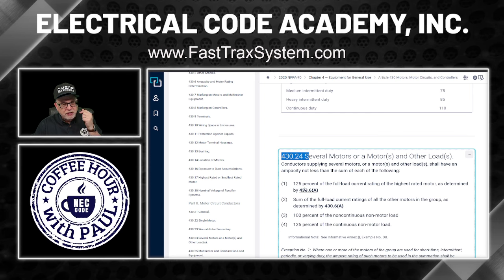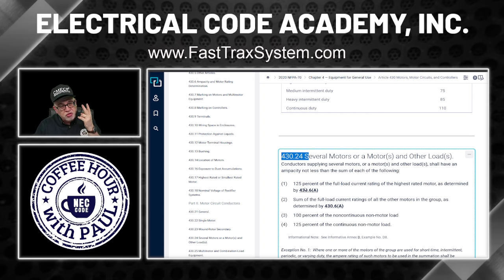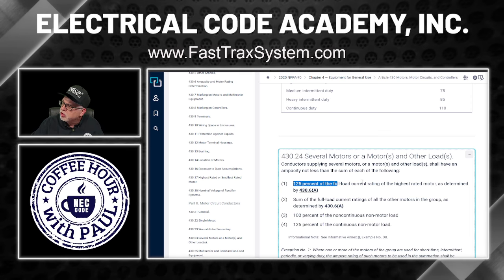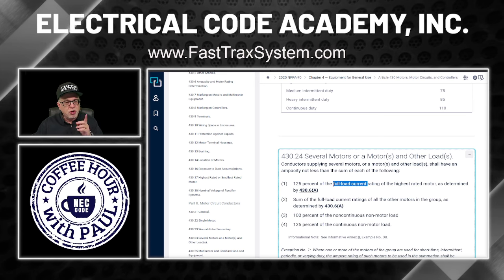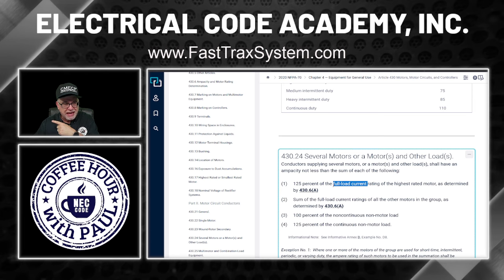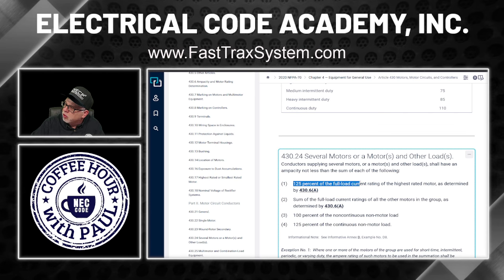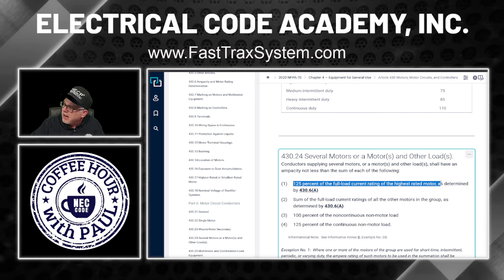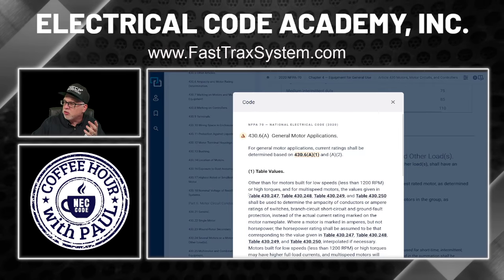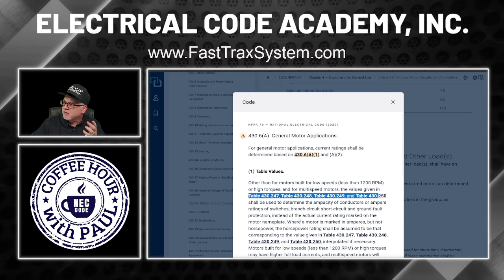Remember what our question was? We had 2 motors. It was a 3-phase, 25 horsepower, and there were 2 of them. Here's what it says. It says 125% of the full load current. Where do you go to get full load currents, folks? You go to the back of Article 430 to those tables, right? It says 125% of the full load current rating of the highest rated motor as determined by 430.6(A). Well, 430.6(A) is what tells you the tables that you go to, right? That's where it tells you about these tables.